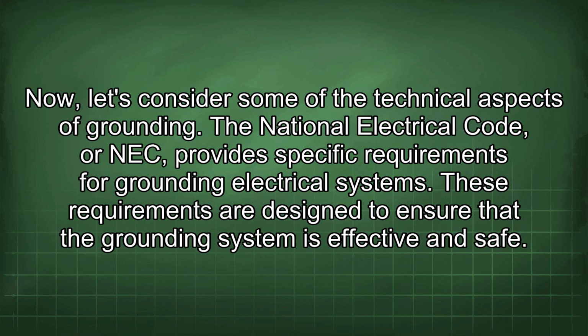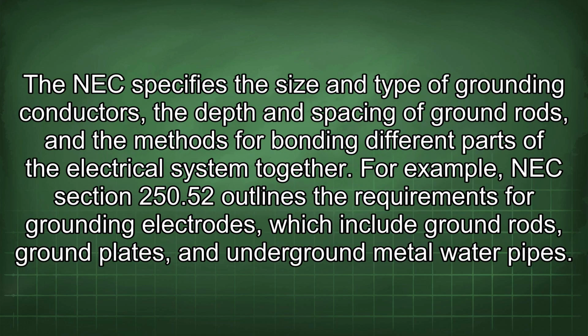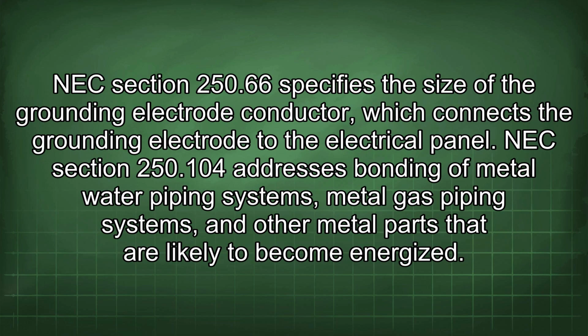The National Electrical Code, or NEC, provides specific requirements for grounding electrical systems. These requirements are designed to ensure that the grounding system is effective and safe. The NEC specifies the size and type of grounding conductors, the depth and spacing of ground rods, and the methods for bonding different parts of the electrical system together. For example, NEC Section 250.52 outlines the requirements for grounding electrodes, which include ground rods, ground plates, and underground metal water pipes. NEC Section 250.66 specifies the size of the grounding electrode conductor, which connects the grounding electrode to the electrical panel.